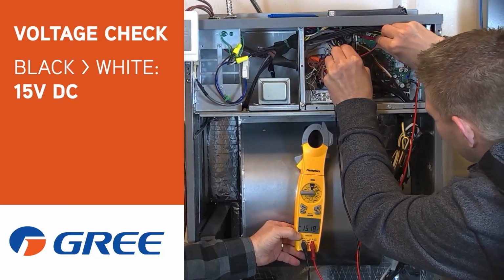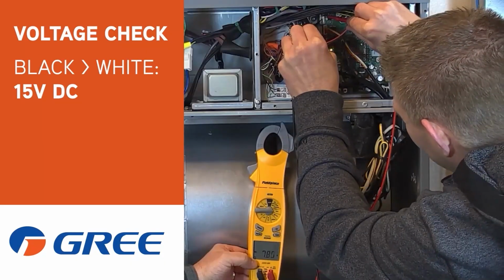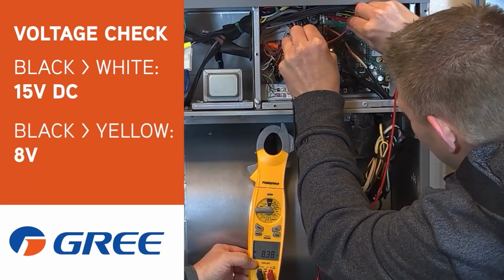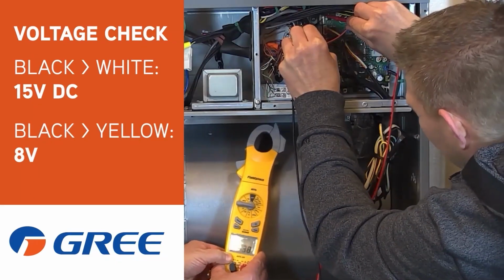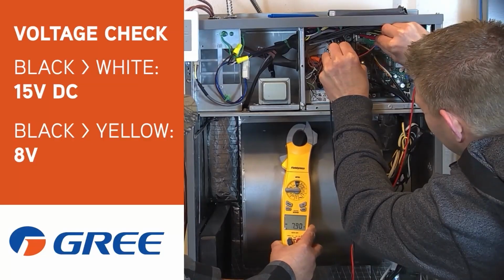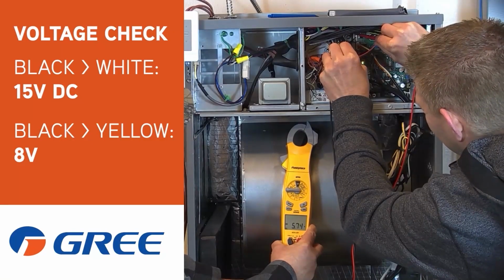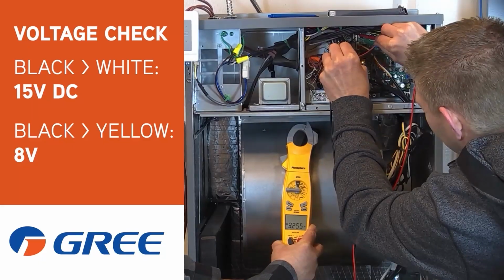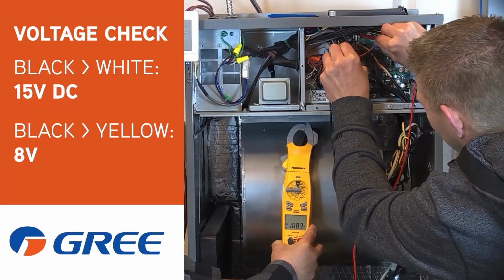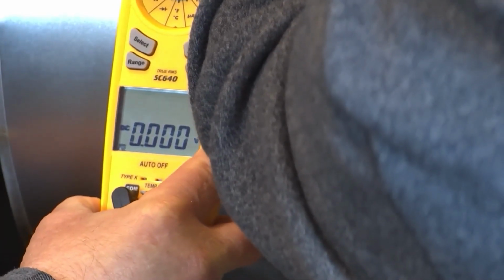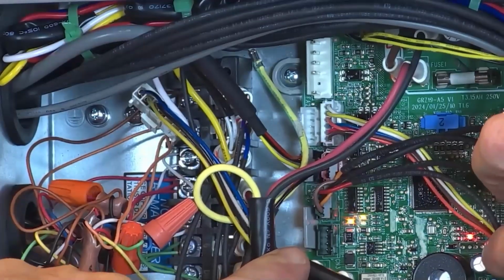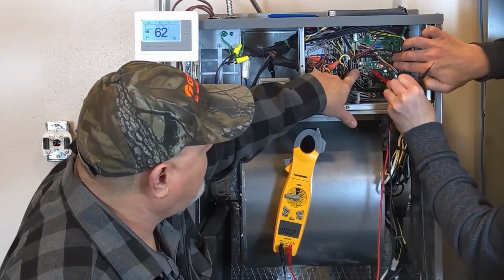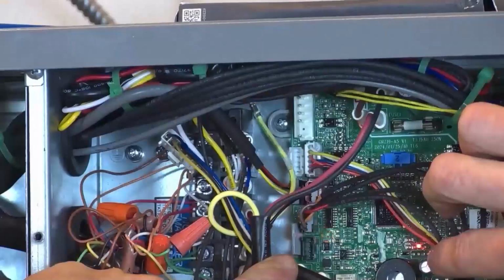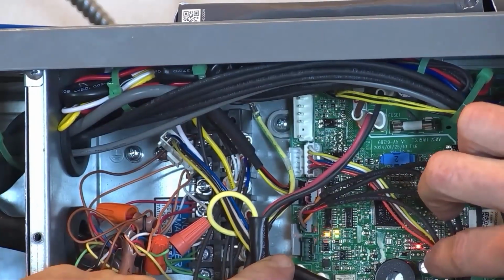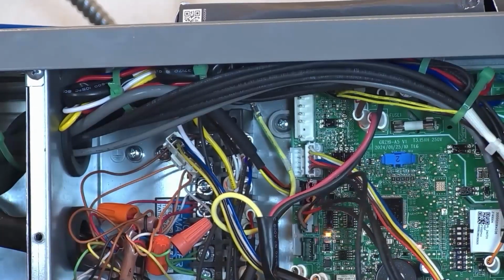Now move to the next pin, black to yellow, and you've got 8 volts — so the board is giving us our signal. Now it's dropping back down; it may try again and bounce the voltage back up. Is the green light blinking on that board? Not yet, it just started blinking. Once that green light starts blinking, it's no longer going to give you the PWM signal, so you've got to power cycle it or wait a little bit — it'll try again. Go ahead and put the meter lead back up there.